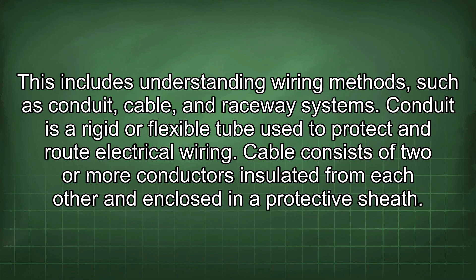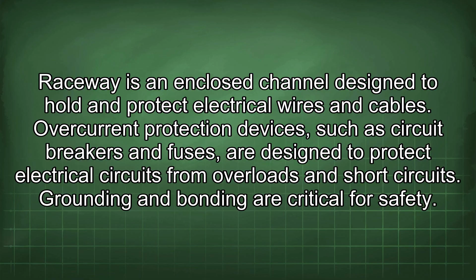Overcurrent protection devices, such as circuit breakers and fuses, are designed to protect electrical circuits from overloads and short circuits. Grounding and bonding are critical for safety. Grounding provides a path for fault current to flow back to the source, tripping the overcurrent protection device. Bonding connects metal parts together to create a low impedance path for fault current.